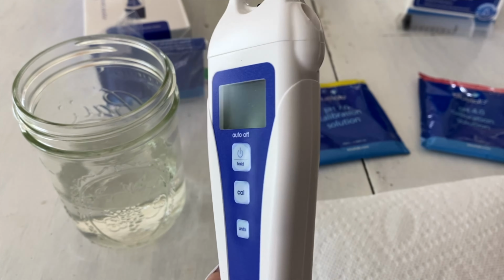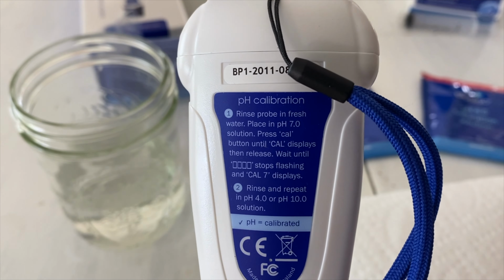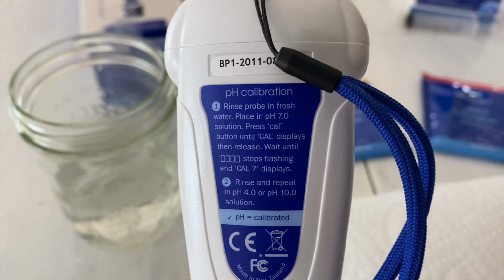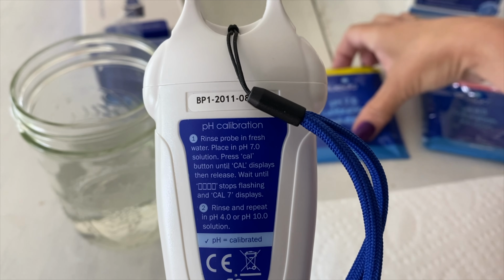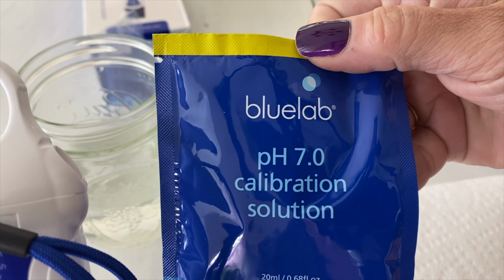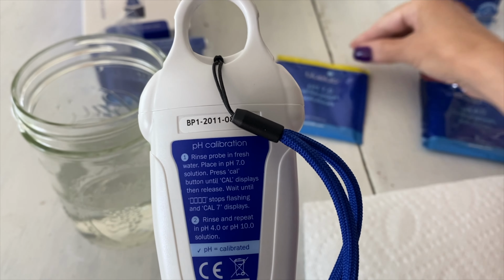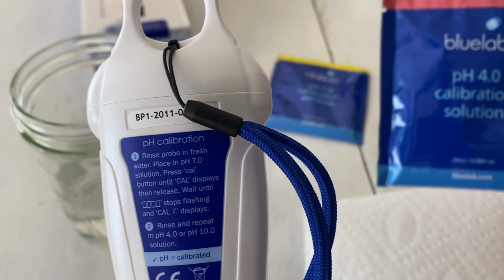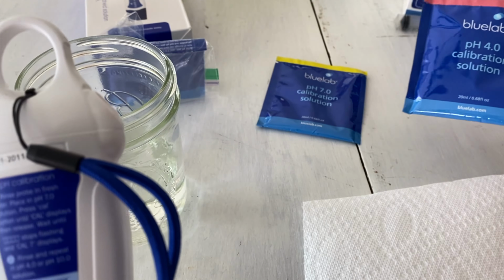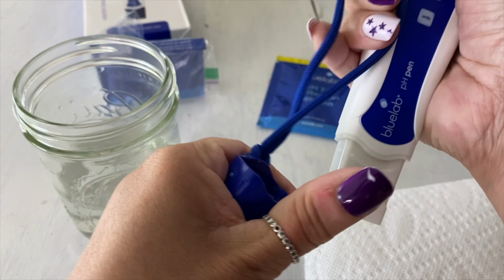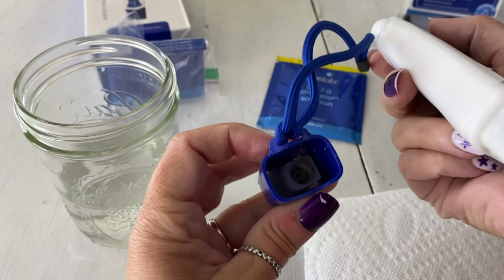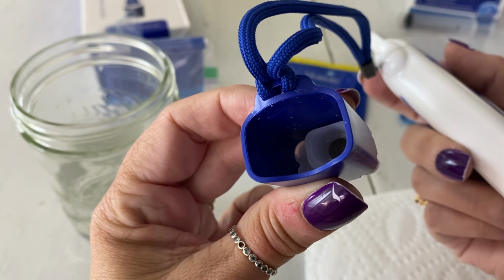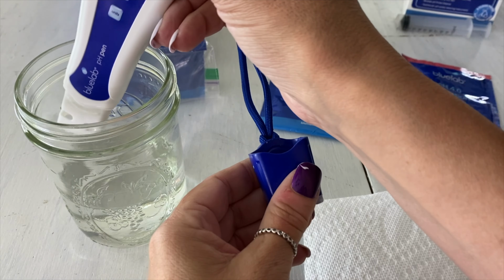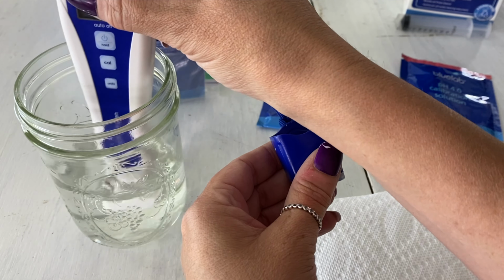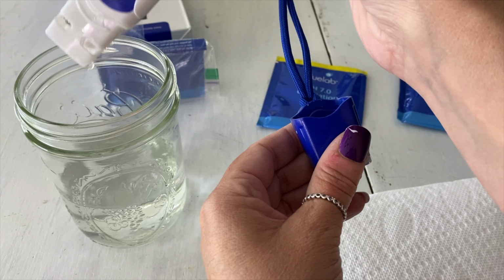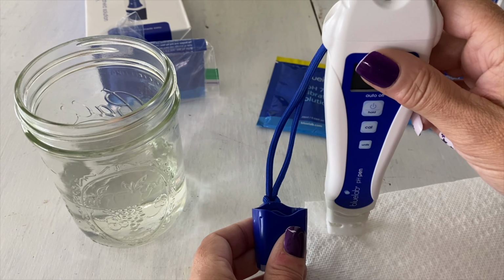First, you notice that there are instructions right on the back of the unit. Then you're going to have a 2-point calibration, one being a 7.0 and the other being a 4.0. It's super easy. You're gonna remove your cap, and this is also where you can put your solution to keep it wet. Then you're just gonna rinse it with plain water and just tap off any excess from that.